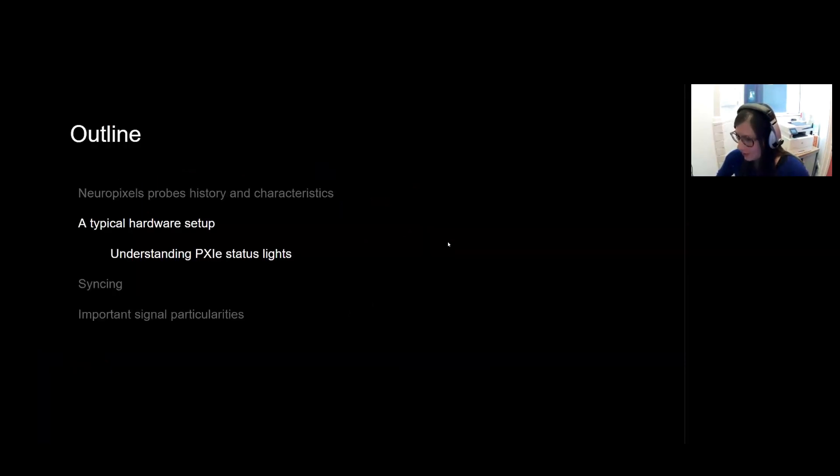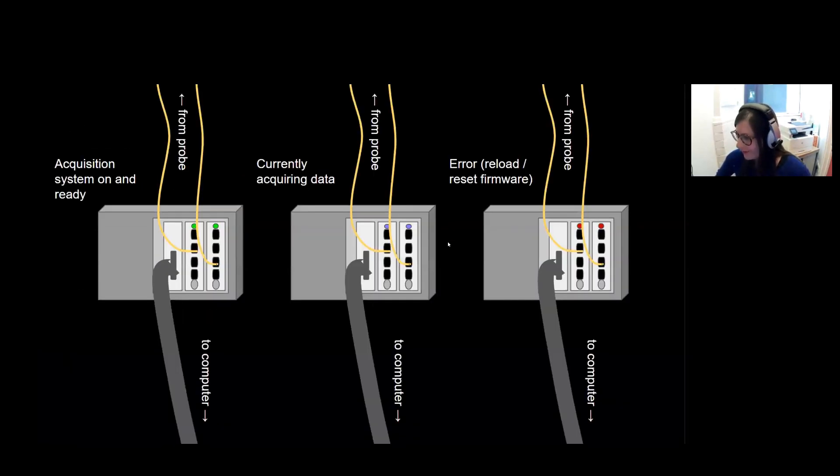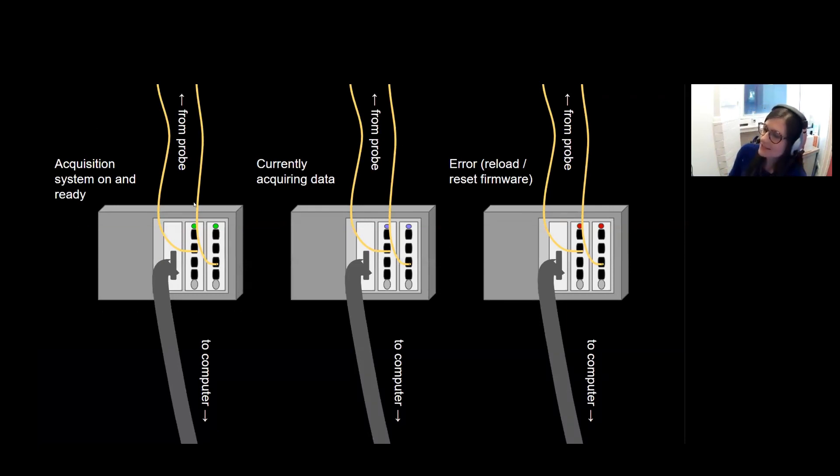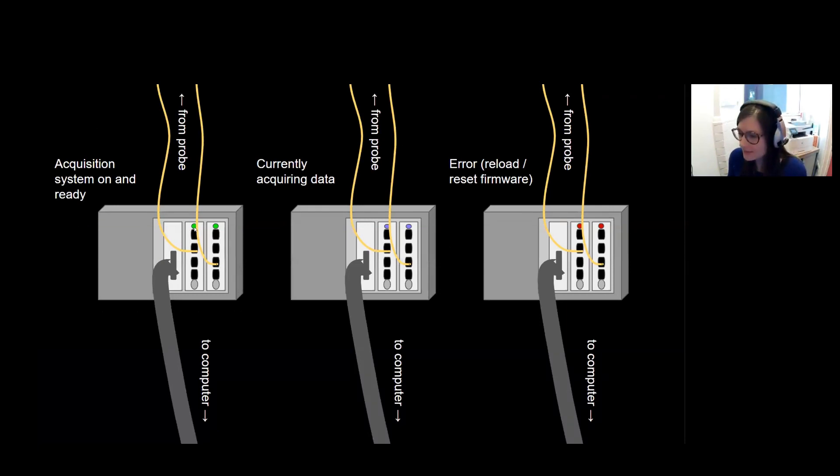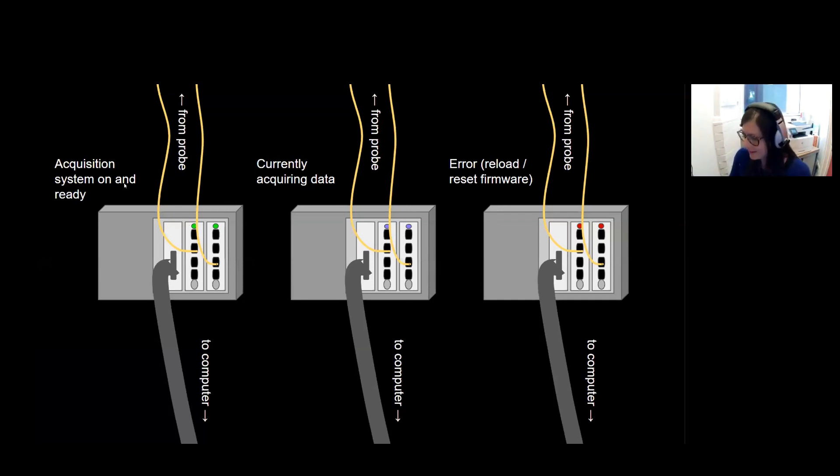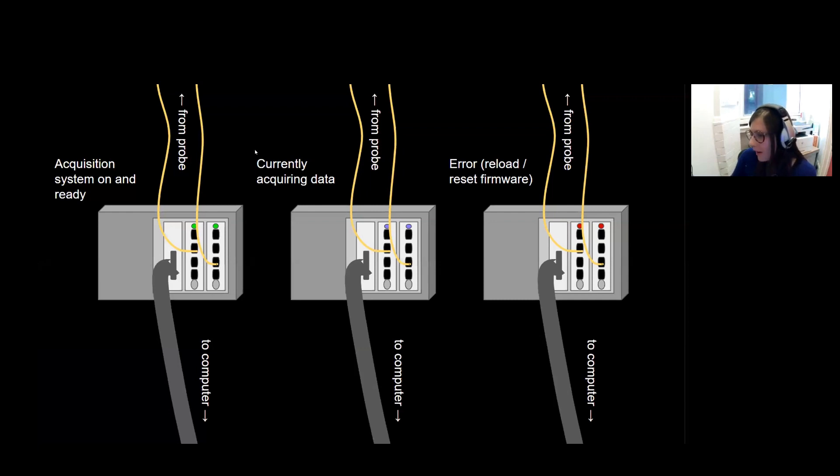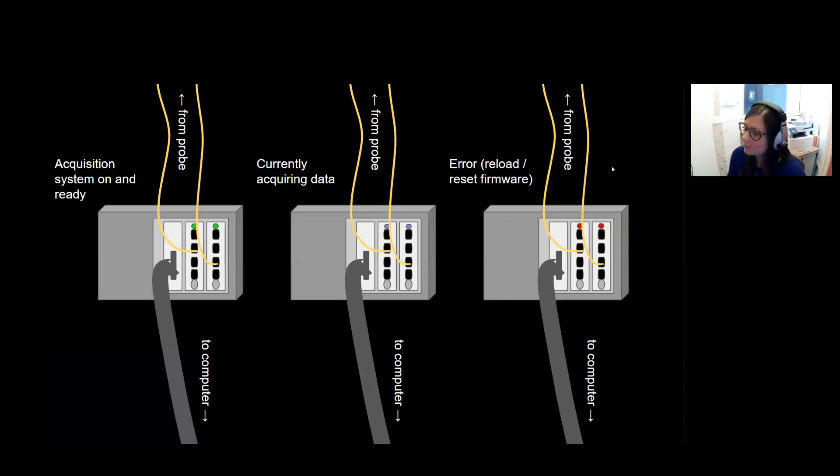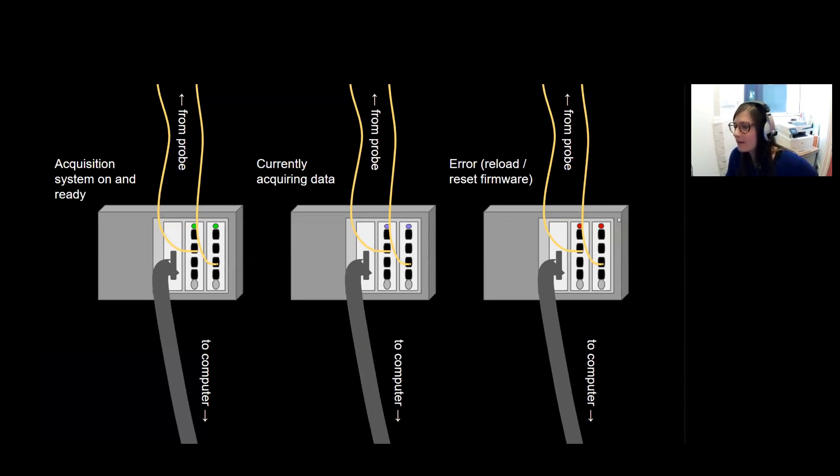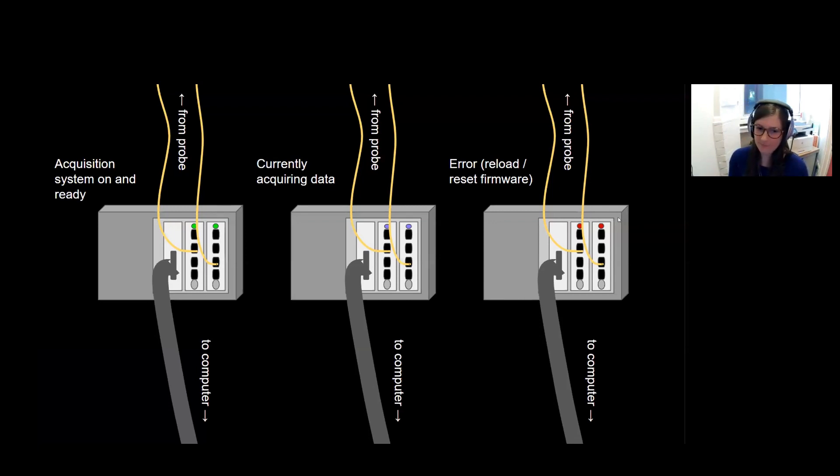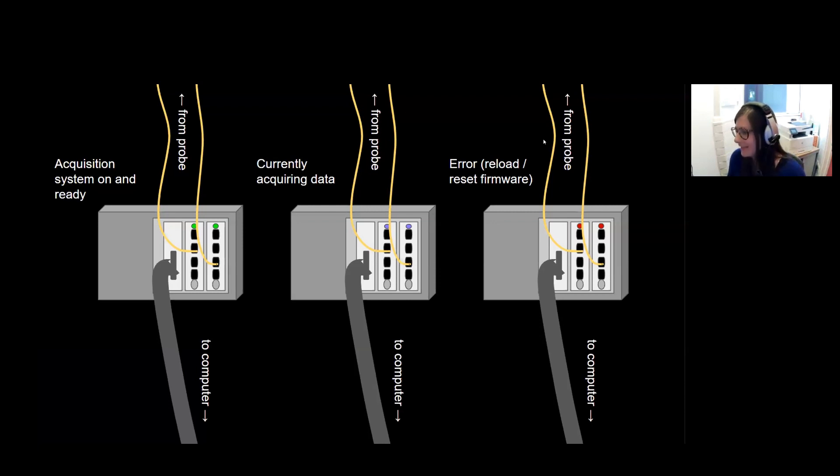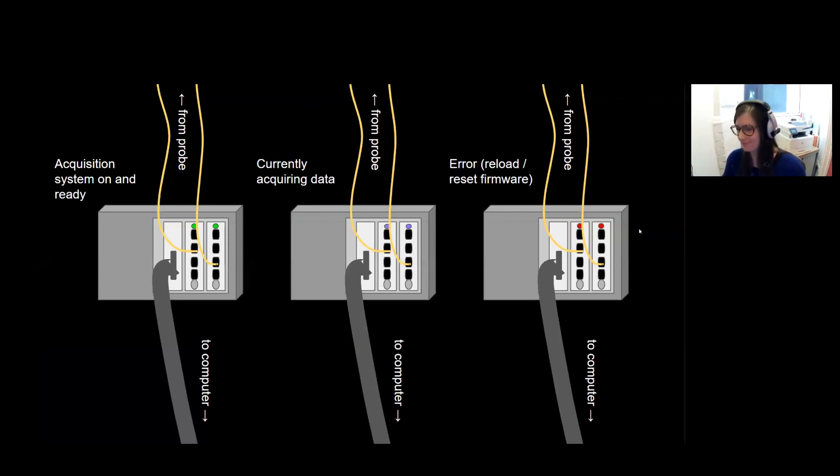We're just going to go briefly over what this looks like when you're recording. So your PXIE chassis has different status lights and it will typically have a green status light if your acquisition system is on and ready. If you're currently acquiring data, it'll be purple. And if there's some sort of error and perhaps there's a software firmware error, it will be red or might even be blinking red and green. So it's important to take a look at these lights when you're trying to record in order to diagnose and check what's going on.